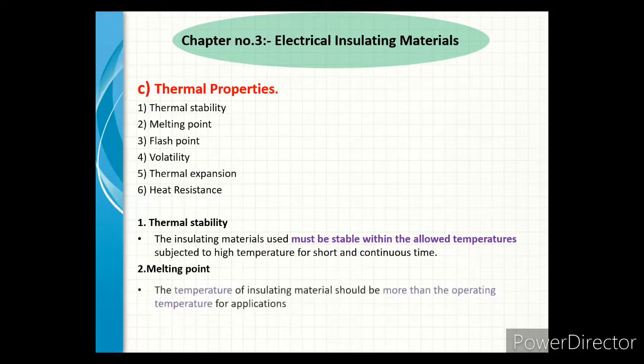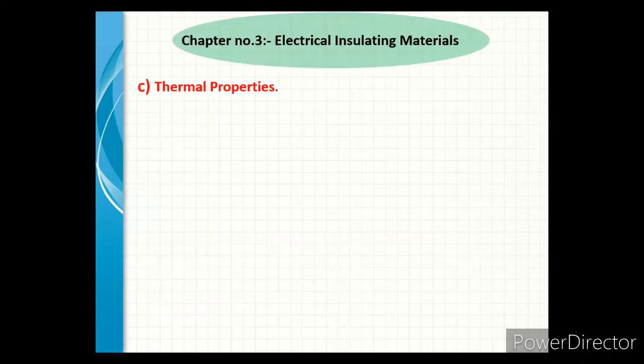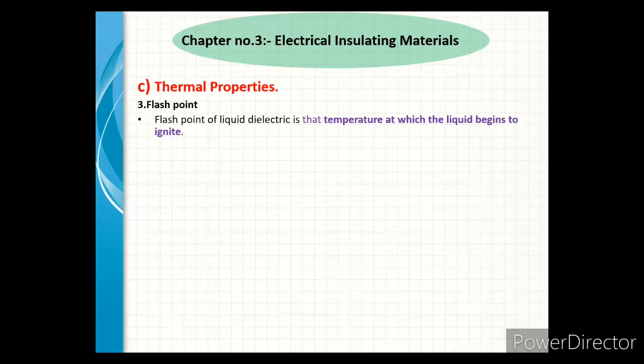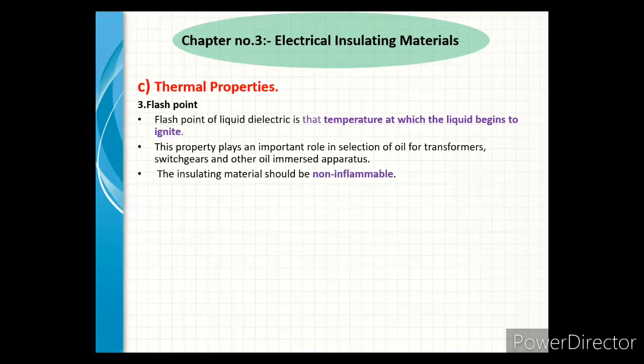Melting point: the temperature of insulating material should be more than the operating temperature for a particular application. Flash point: the flash point of a liquid dielectric is that temperature at which the liquid begins to ignite. This property plays an important role in the selection of oil for transformers, switchgear, and other oil-immersed apparatus.